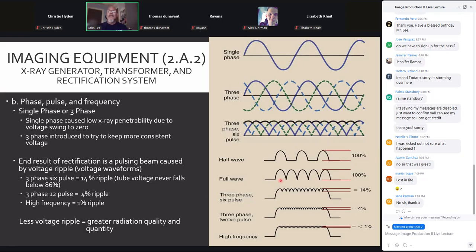All right. So what we did was throw in some more electrical components, get 3 phases in there. Now, if single phase gives us 120 pulses per second, positive and negative, we flip that and now we've got full wave rectified, 120 pulses per second up there. If we just modify it and give us 3 phase, that's 3 lines. 3 times 120 is 360 pulses per second.